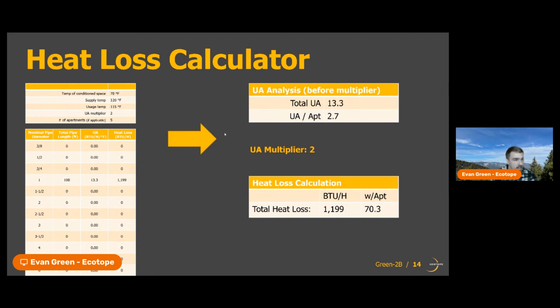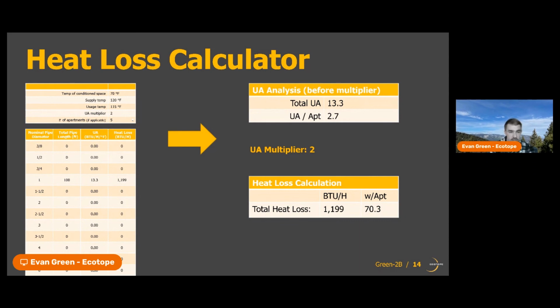The last thing we'll input here, and this is a big one, of course, and this is where you're going to have the most lift, is we're going to tally up all the pipe lengths of different pipe sizes, and we'll input those in total feet of pipe of each pipe size. Then the calculator will pair each pipe size with a certain insulation thickness, and it will calculate how much heat loss you have throughout the entire system, based off this average temperature throughout the distribution loop, as well as the overall surface area of your pipe system and the thickness of insulation associated with each size of pipe.